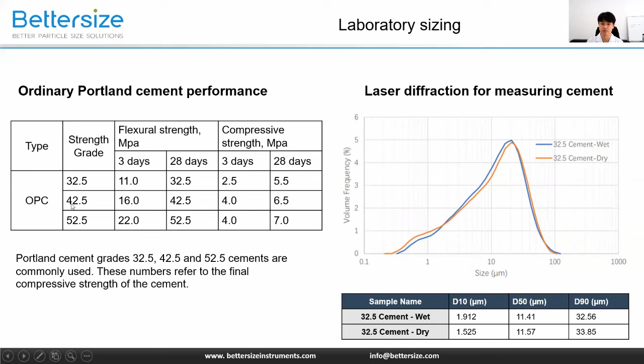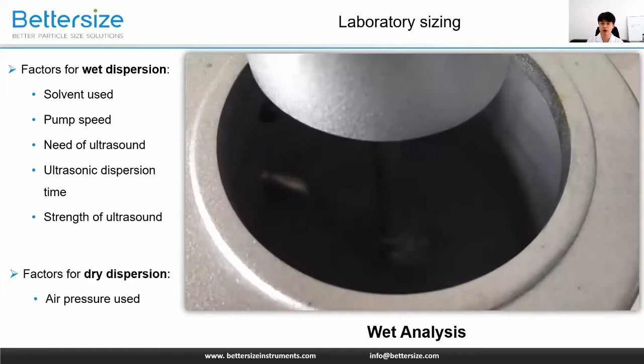With the laser diffraction analyzer, we are able to measure the fineness of cement in its natural dry state or as a wet dispersion, using industrial alcohol such as propanol or ethanol. As can be seen, both wet and dry dispersion methods yield almost the same result. Here is the wet analysis process when I measure cement particles. As you see, cement is well dispersed in a small amount of ethanol, and the results can be provided in less than 10 seconds. However, due to lower running costs, better statistical representation, and easier usage, the dry method is preferred rather than wet analysis in the cement industry.